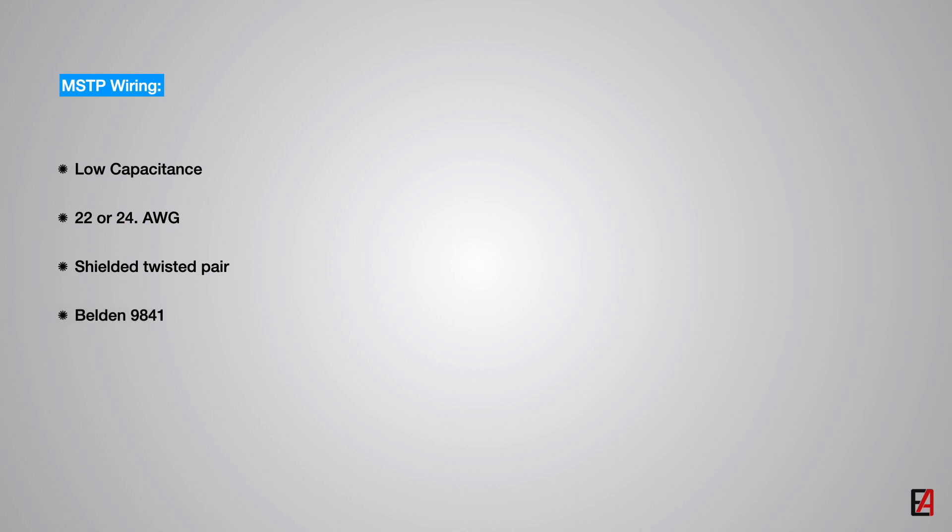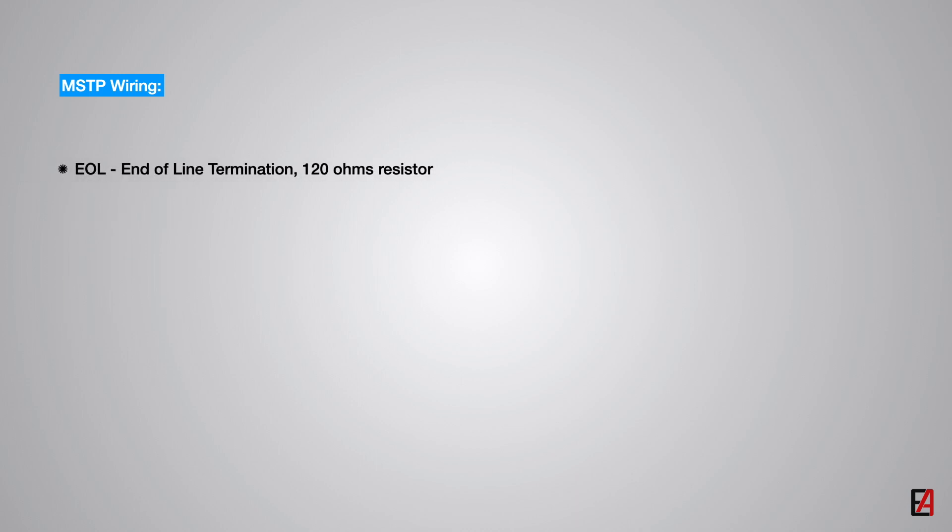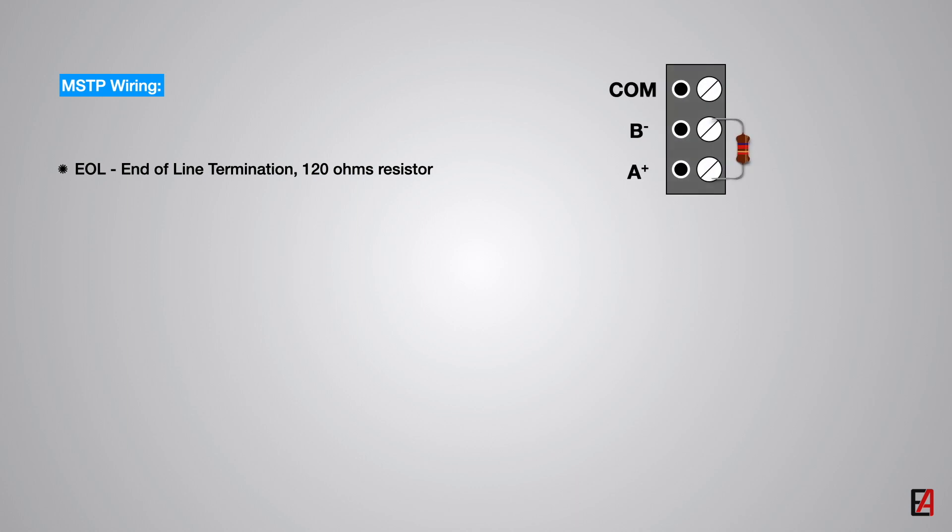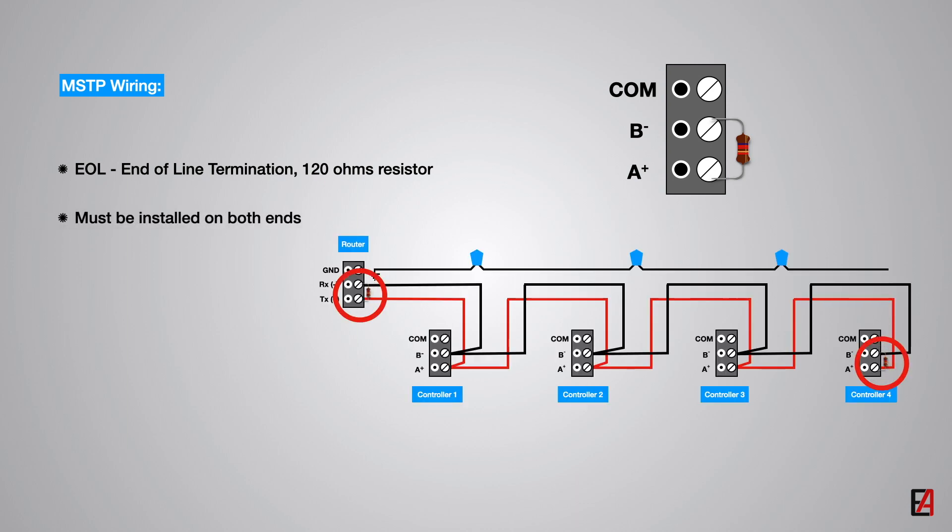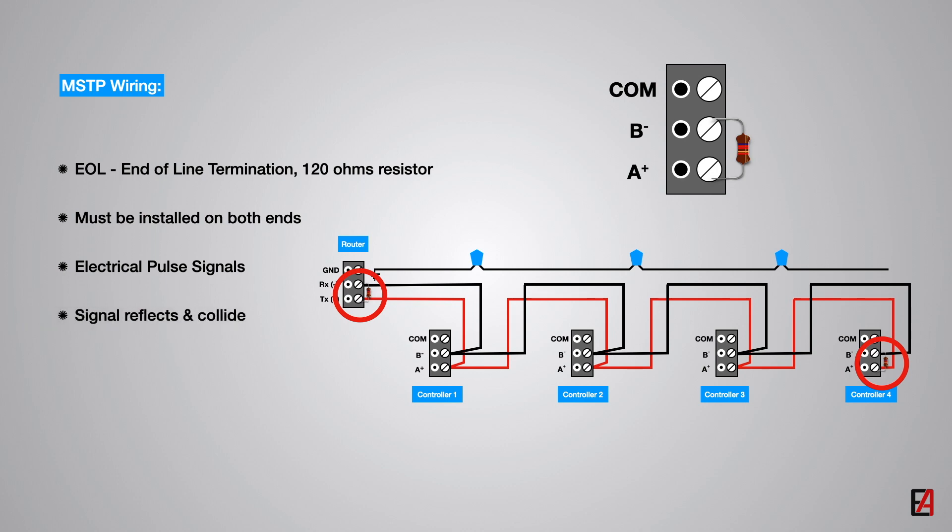Now we will see about the importance of EOL for the MSTP network. EOL stands for end-of-line termination. In order to avoid reflection issues, end-of-line resistors typically of 120 ohms must be installed at both ends of the physical network wire. As the communication is achieved by electrical pulse signal, when no end-of-line resistors are installed, the pulse signal reflects backwards and collides with other data pulses. The end-of-line resistor absorbs the pulse energy and dissipates as heat. So EOL must always be installed on the MSTP network.